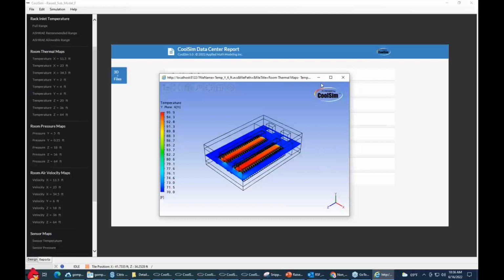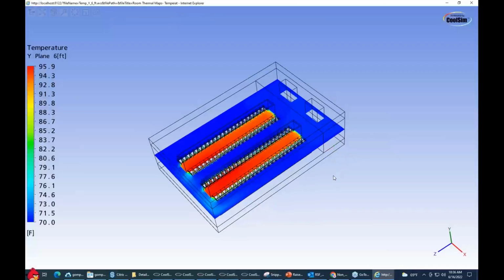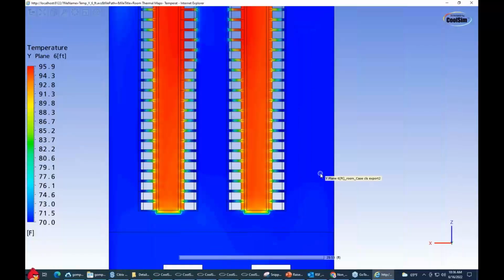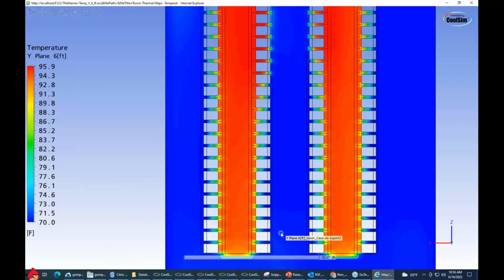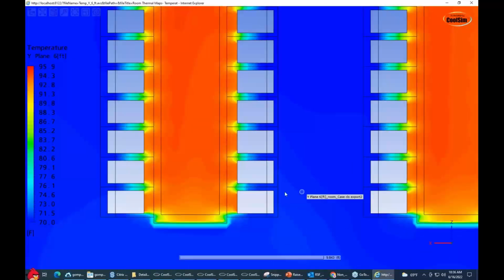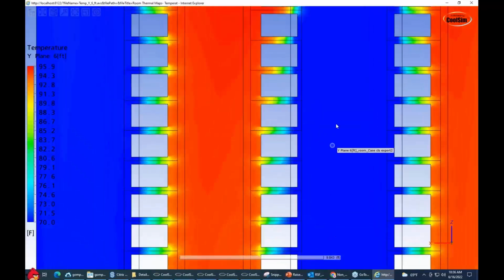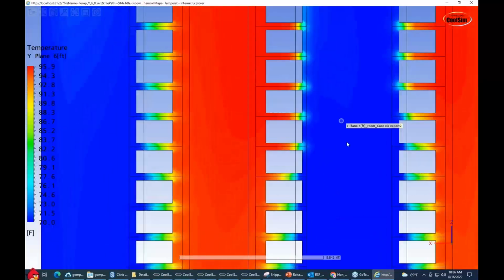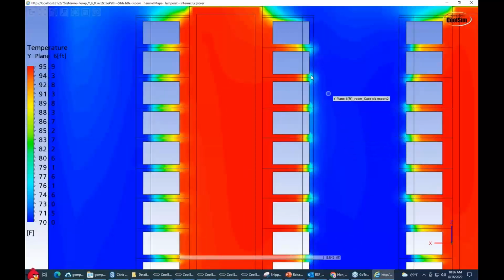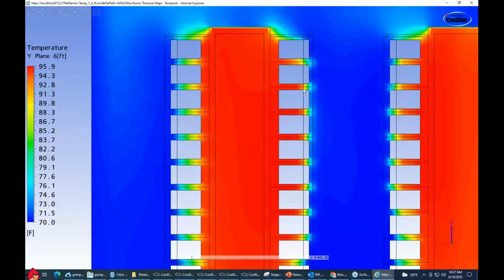And you'll see a similar behavior, but it's just a little easier to manage it now. So let's take a look. Again, top view. You see they're much better than they were. Certainly down here, where it was leaking through that rack rail earlier, it's not anymore. I have plenty there, and as we move to the back and we see that pressure differential, it starts squirting out again. So down here on this design, I had a little bit of problem in this range, but still good over here, and this one could be managed.